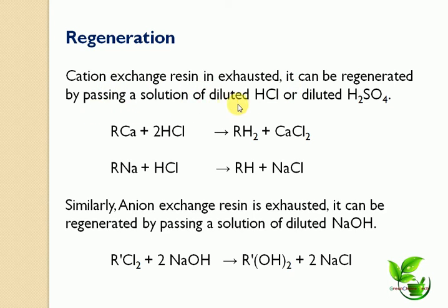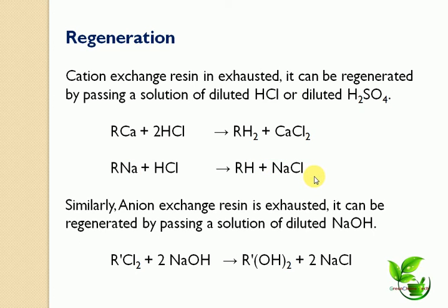The exhausted cationic exchange resin is regenerated by passing diluted hydrochloric acid or diluted sulfuric acid through it. For example, RCa + 2HCl → RH₂ + CaCl₂, and RNa + HCl → RH + NaCl, restoring the resin. Similarly, the exhausted anionic exchange resin is regenerated by passing diluted sodium hydroxide: RCl₂ + 2NaOH → R(OH)₂ + 2NaCl. Both cationic and anionic resins are thus regenerated for reuse.